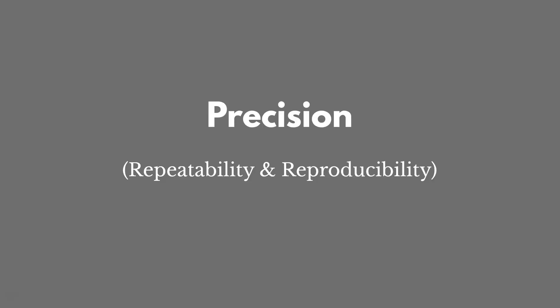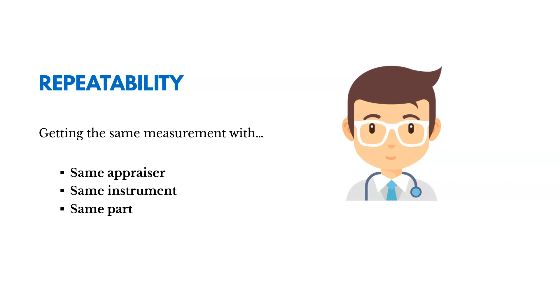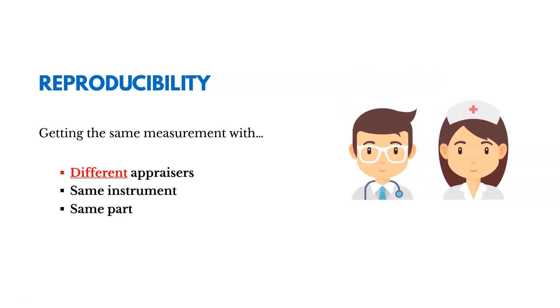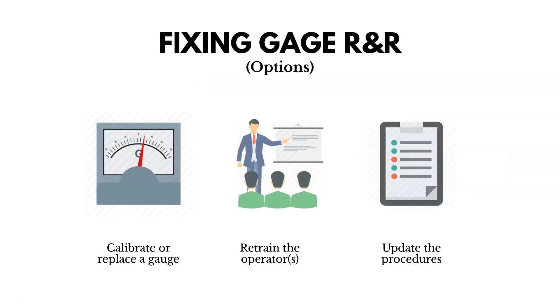Let's talk about these each in a little more detail. Starting with precision. So again, repeatability is getting the same measurement with the same appraiser, the same instrument, and the same part. It's like the doctor, measuring your blood pressure using the same instrument. Then reproducibility is getting the same measurement with different people, like the doctor and the nurse, but using the same instrument to monitor your blood pressure. Now, if we see issues with what we call gauge R&R, gauge repeatability and reproducibility, some of our options are to try to calibrate or replace our gauge, to retrain our operators, or to update our procedures. Making sure they provide enough detail and that they're actually accurate. The steps that we've listed in the procedure are correct.